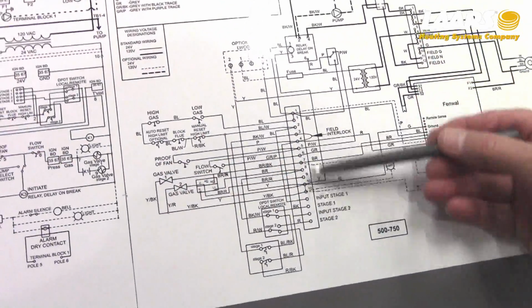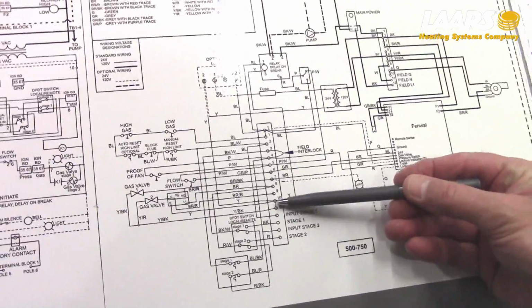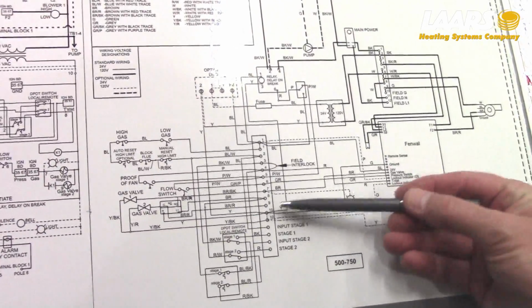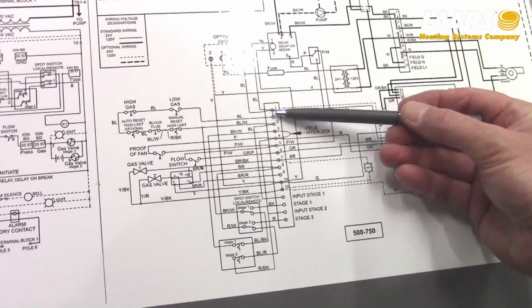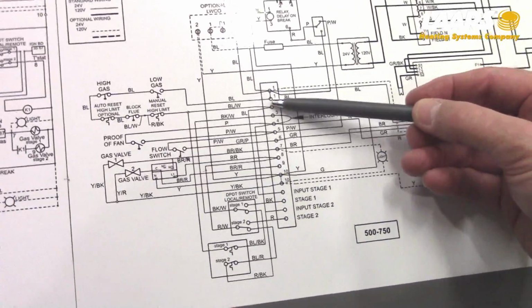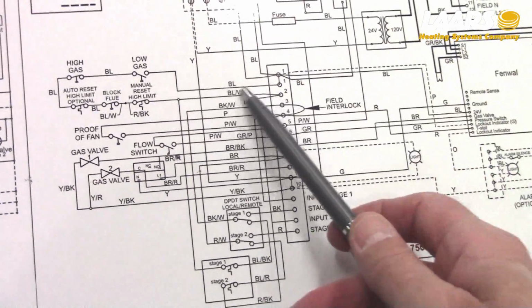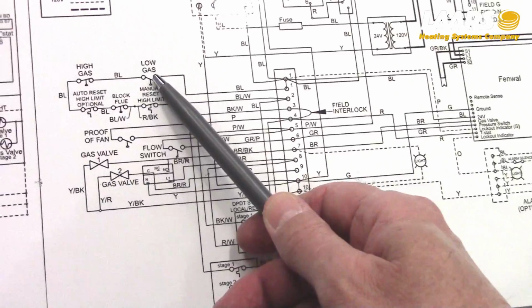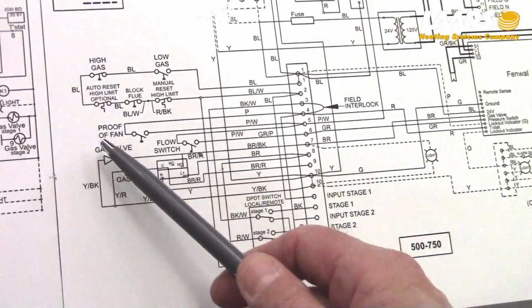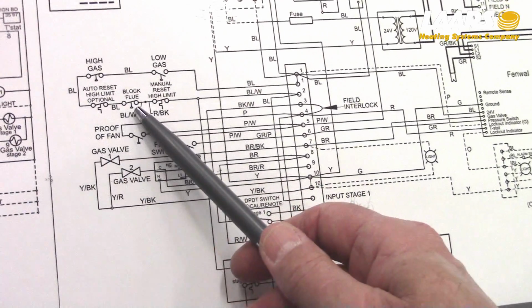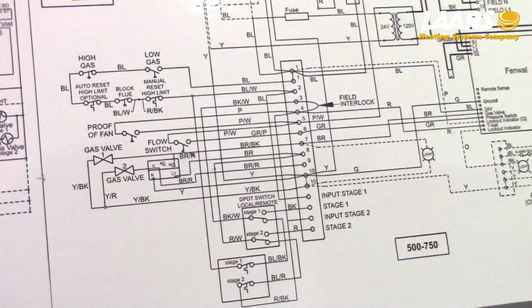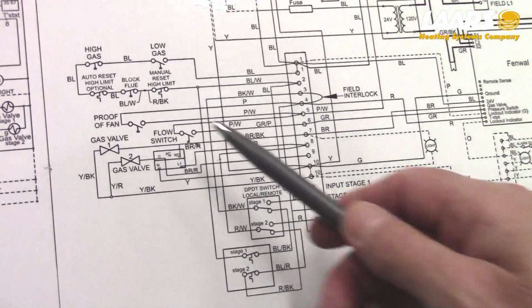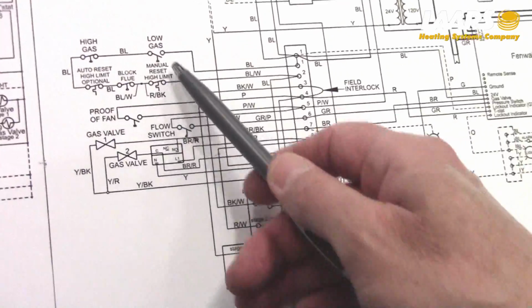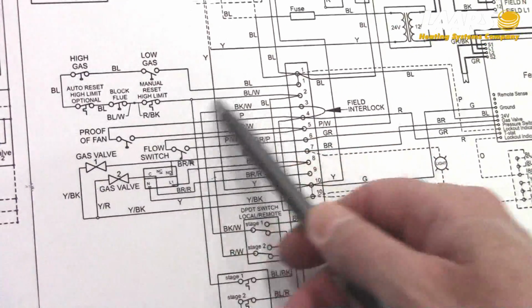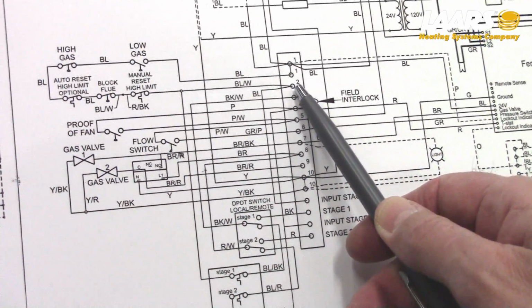Here are our terminal strips. Okay, I mentioned number 10 is 24 volt common with the yellow wires. Terminal 1 brings power in, 1 and 1A. So that goes off to our low gas pressure switch, our high gas pressure switch, the limit, blocked flue, manual reset high limit. Okay, and then back to terminal 2. So what we have here was the open gas pressure switch to terminal 2, which I've just reset.